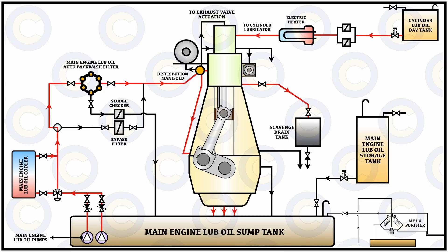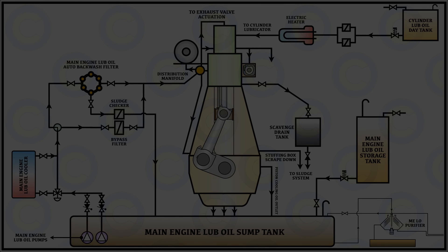In modern engines, scrapedown analysis is a periodical routine carried out using a dedicated line for drawing samples. If a permanent assembly or system is installed, the valves will be aligned so you can directly draw the oil and test it. The piston cooling oil return line allows oil to go back into the sump separately. This is one thing you will also find in high-pressure designs, as discussed, for certain types of engines.